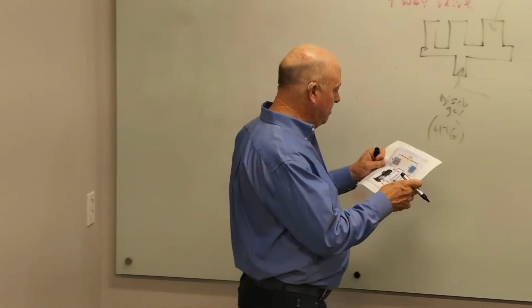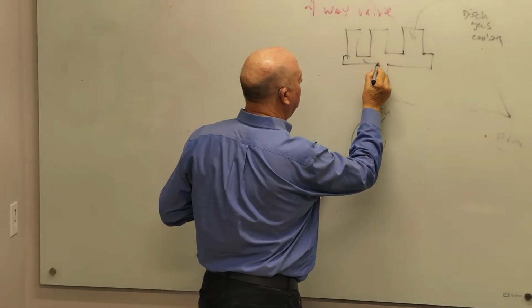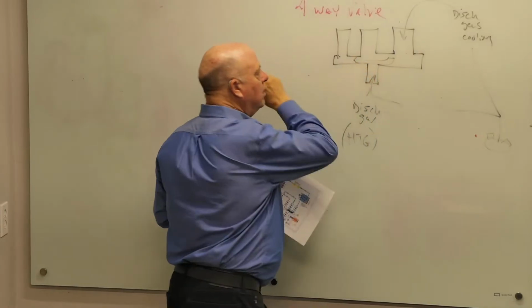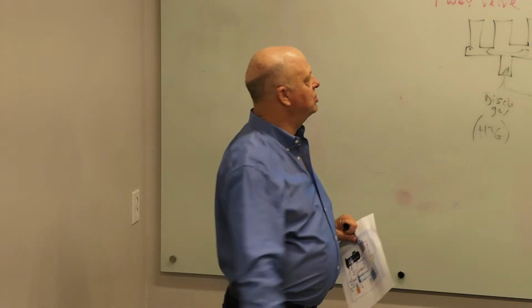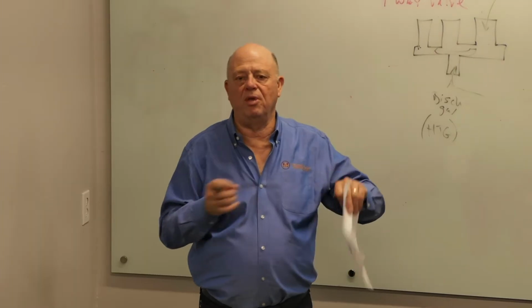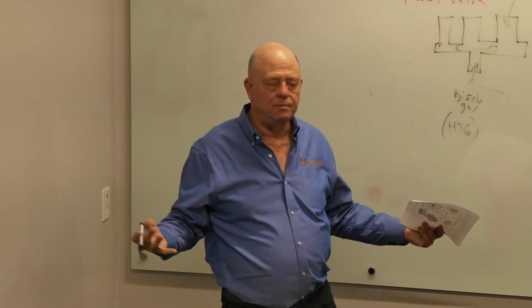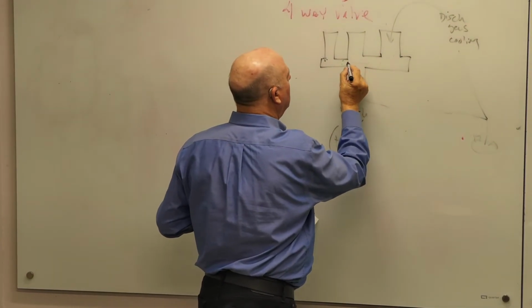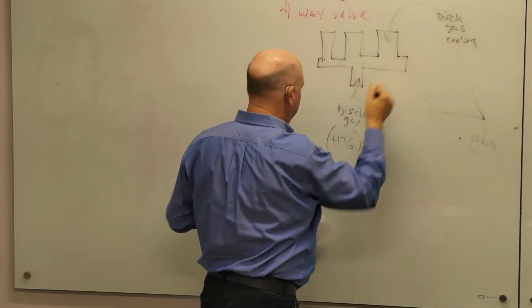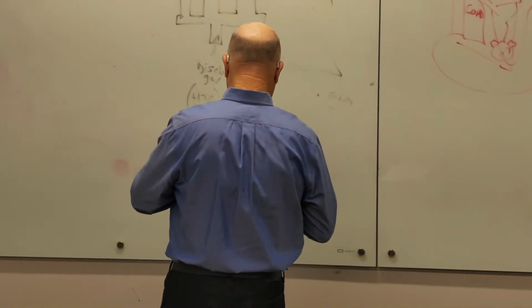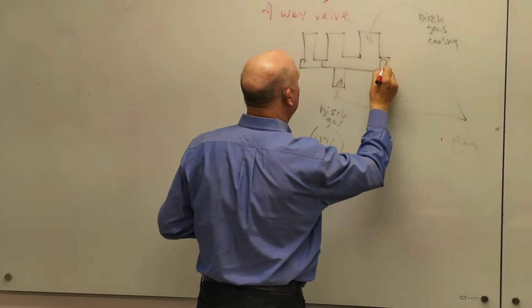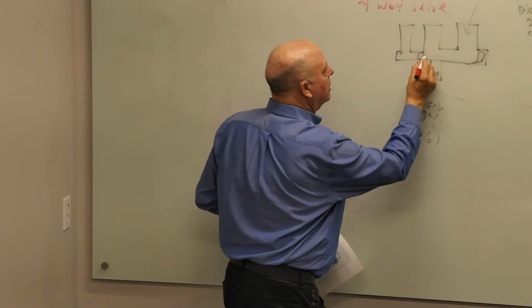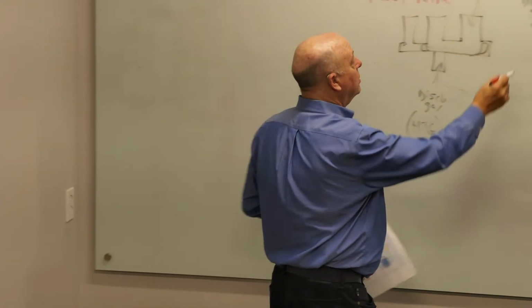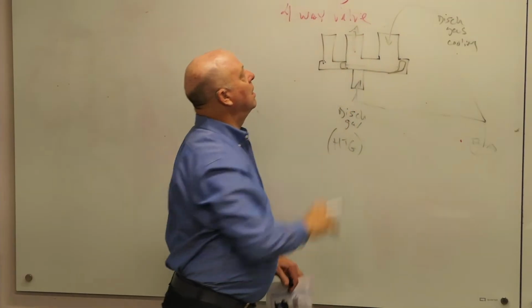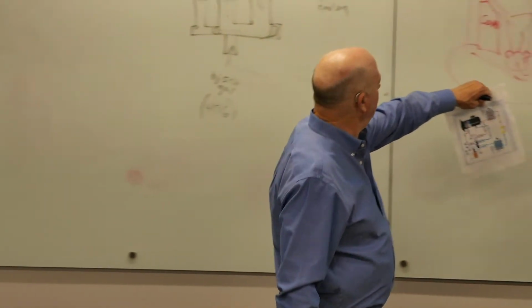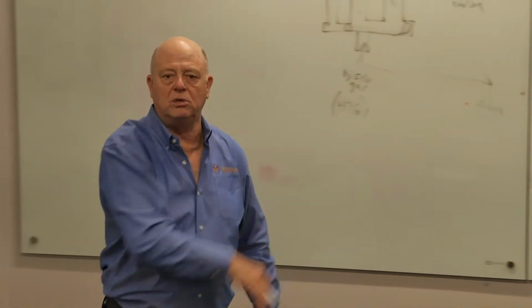And that's the case with the reversing valve. How does it know? In the cooling mode, there's a little doohickey that can slide. And there's typically a magnet or an electromagnet, something that causes it to move depending upon which mode it's in. So if we're in the cooling mode, it's sitting like this. And so here it is. It's blocked off this one, hasn't it? And in the cooling mode, it goes in here, it goes out there, and it's like it wasn't even there. It's done nothing. All we've done is we've stuck it in the standard cooling thing, and when it's in that position, it works just like cooling, and there's nothing different.